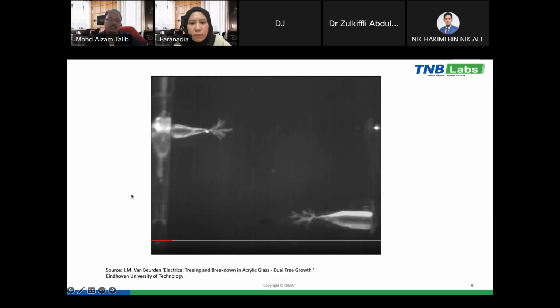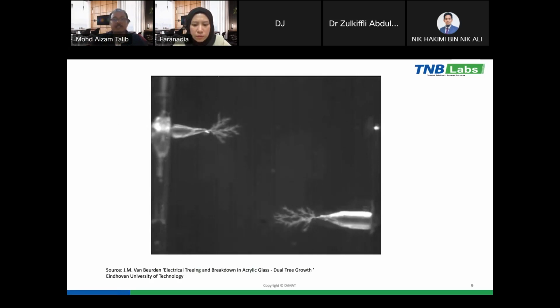Okay, this is an example of the electrical treeing, or the partial discharge that occurs in solid insulation. During this time, the insulation can function as it is designed. But as we can see, the partial discharge will grow over time, and then finally it will break the two terminals between the high voltage and the low voltage, or between the high voltage and the ground. So it will cause the puncture of the insulation system. And then from the partial discharge, finally it will turn into discharge or arcing activities.